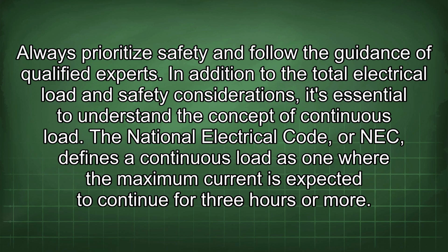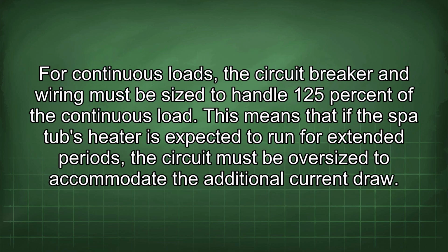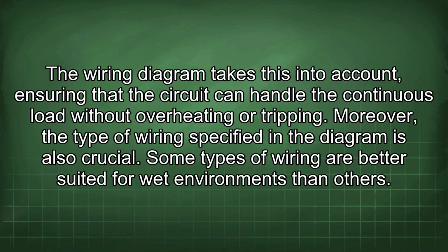In addition to the total electrical load and safety considerations, it's essential to understand the concept of continuous load. The National Electrical Code, or NEC, defines a continuous load as one where the maximum current is expected to continue for 3 hours or more. For continuous loads, the circuit breaker and wiring must be sized to handle 125% of the continuous load. This means that if the spa tub's heater is expected to run for extended periods, the circuit must be oversized to accommodate the additional current draw. The wiring diagram takes this into account, ensuring that the circuit can handle the continuous load without overheating or tripping.